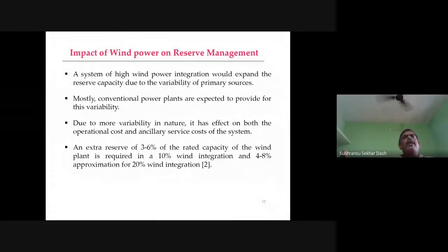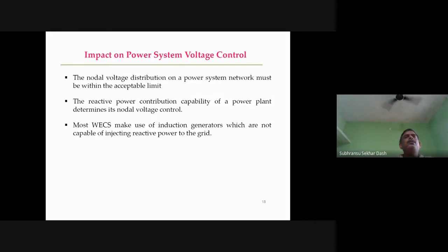The impact of wind power on reserve management. A system of high wind power integration will expand the reserve capacity due to the variability of primary sources. Mostly conventional power plants are expected to provide for that variability. Due to this more variable nature, it has an effect on both the operational cost and ancillary services cost of the system. An extra reserve of 3 to 6% of the rated capacity of wind plant is required in a 10% wind integration, and 4 to 8% for 20% wind integration.